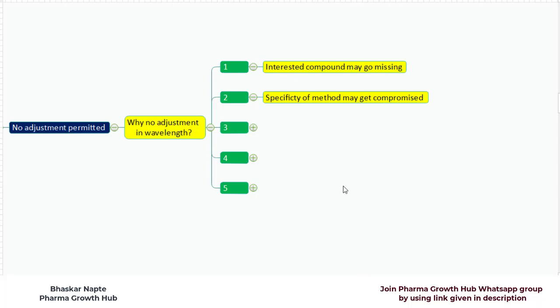But if you decide to change the wavelength, and if that changed wavelength brings interference from the matrix or brings interference from the diluent, your specificity of method will immediately get compromised. There can be interferences coming at the retention time of your analytes, and hence the change in the detection wavelength is not permitted by USP General Chapter 621.